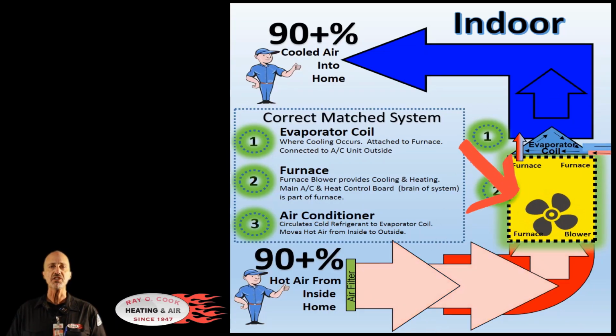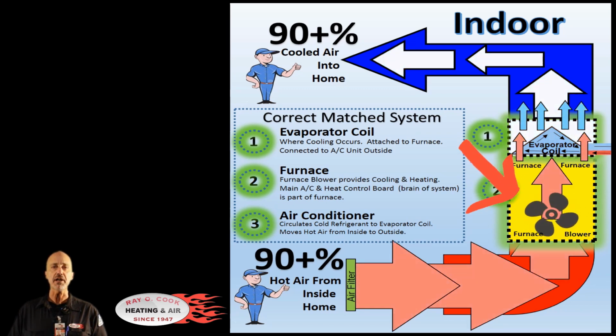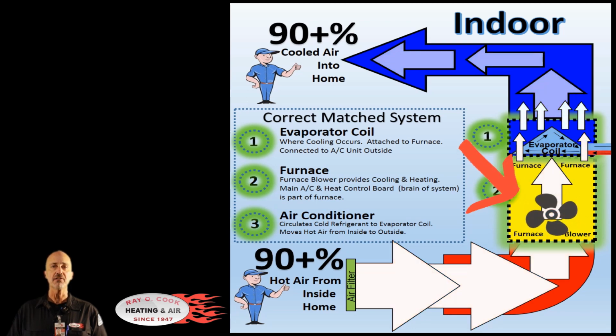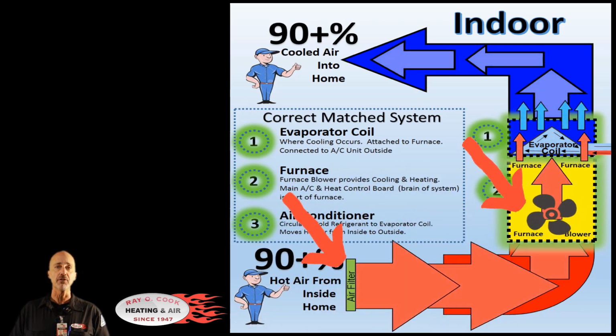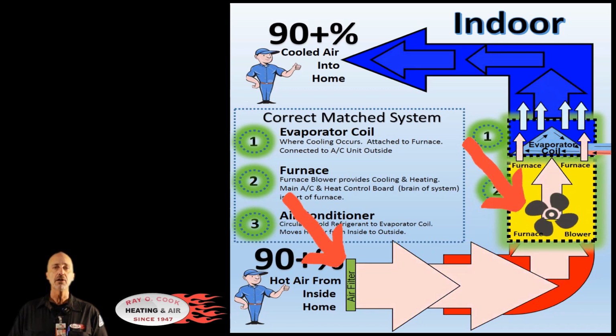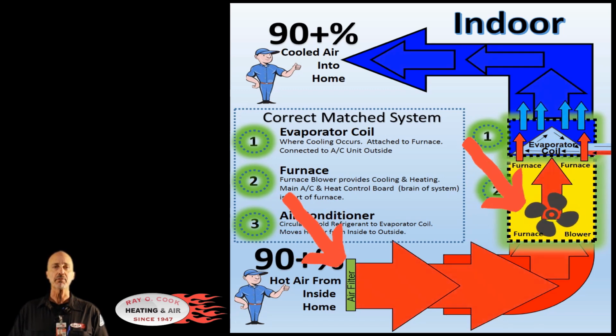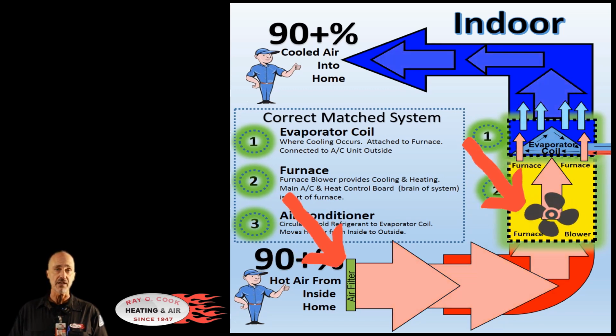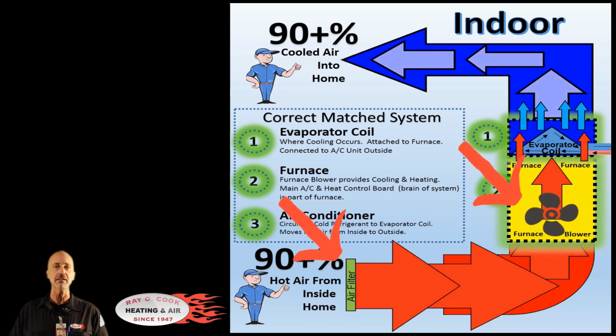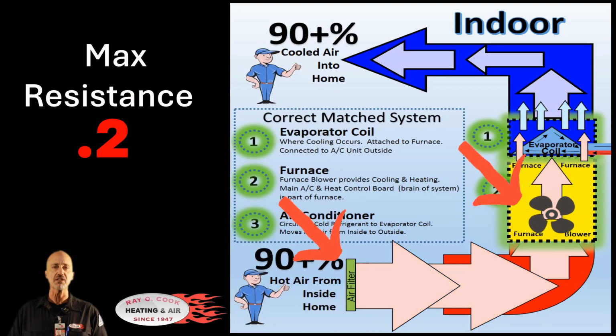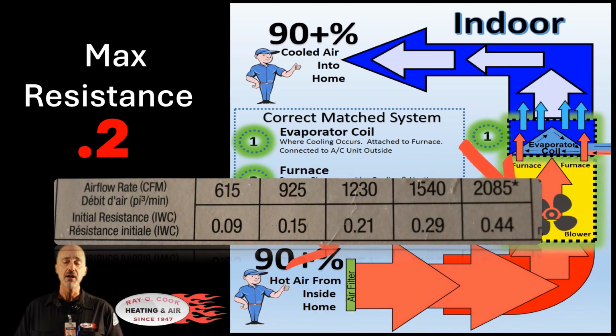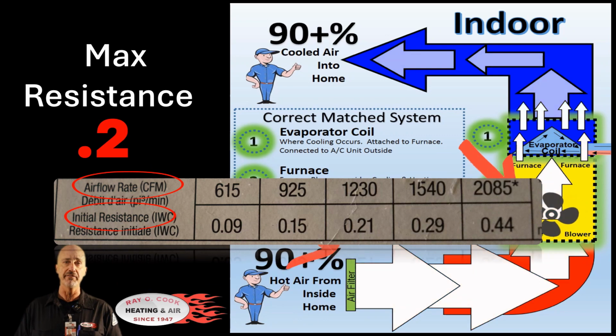Every filter has a resistance rating as well. The fan in your HVAC system has to be able to compensate for all of the restrictions that are found in most systems. Your air filter is one of those restrictions. If we create too much restriction with the filter, your fan will not be able to compensate and provide the amount of cubic feet per minute, CFM, of air that your system needs. We do not want to exceed 0.2 on this resistance rating. Most filters have resistance ratings and CFM ratings printed right on them. It's right on the filter.